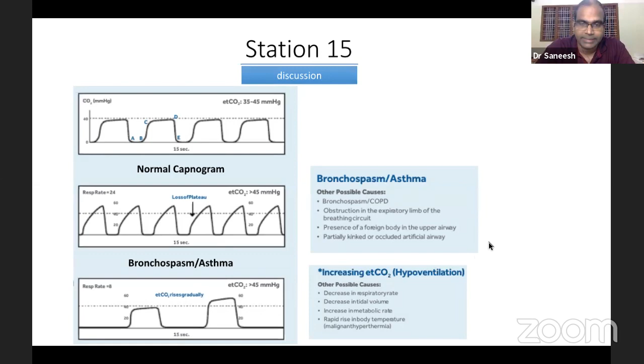Sometimes along with that, they'll give the trend graph also. How about this one, the first one? Here EtCO2 is more than 45 and the baseline is raised, and most probably it is due to rebreathing. Okay. So a rise in the baseline or appearance of inspiratory CO2 is not a good sign. Either your soda lime is exhausted or you have to troubleshoot.